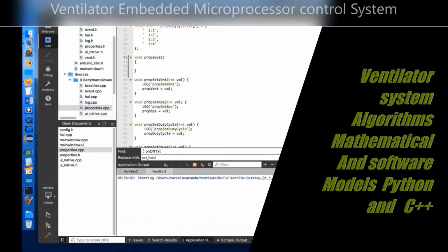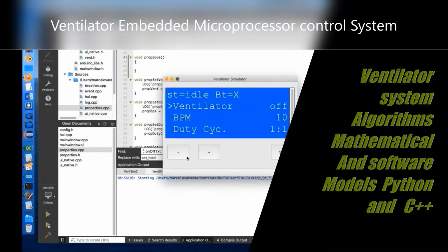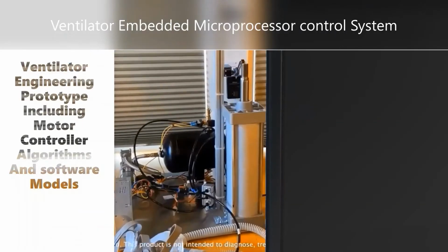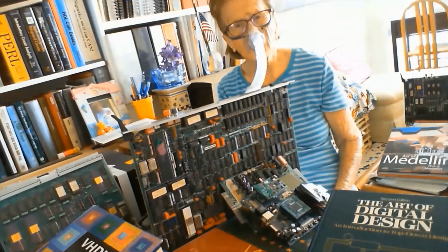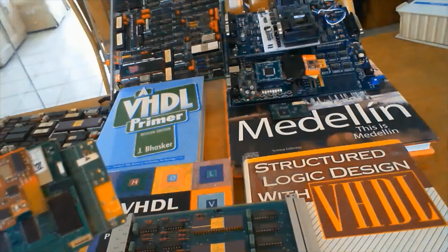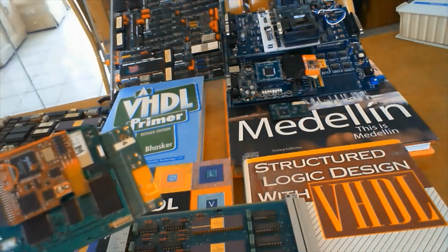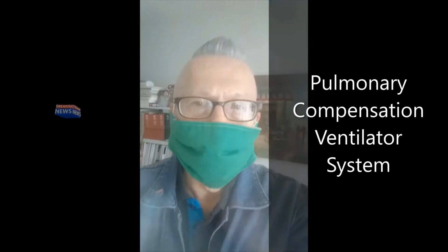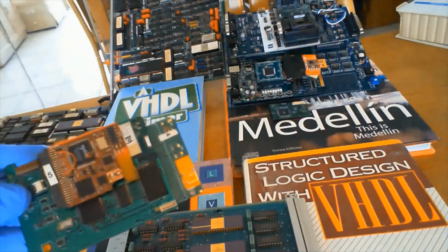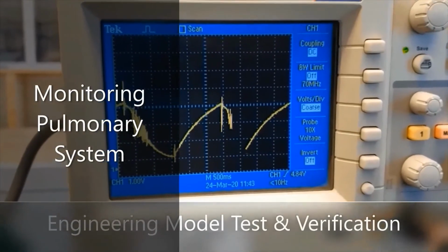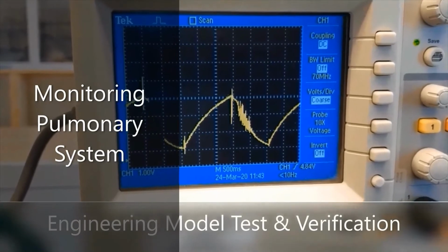As volume measurements are obtained by digital integration of the flow signals, signal processing also significantly contributes to volume accuracy by compensating for drift and leaks, especially during non-invasive ventilation, where leak estimation and compensation algorithms play a significant role.